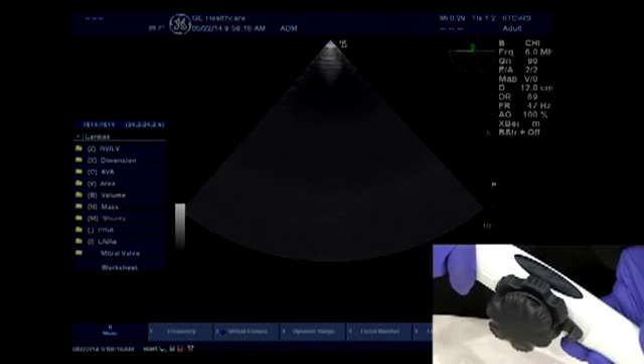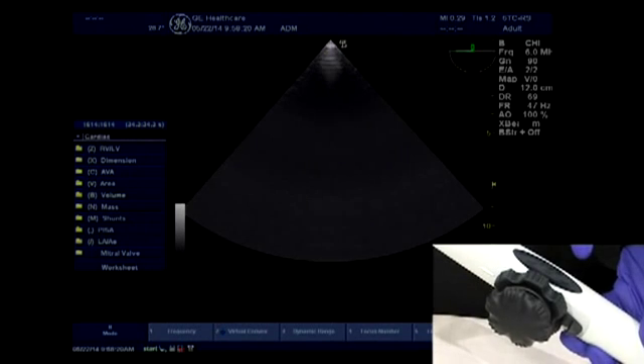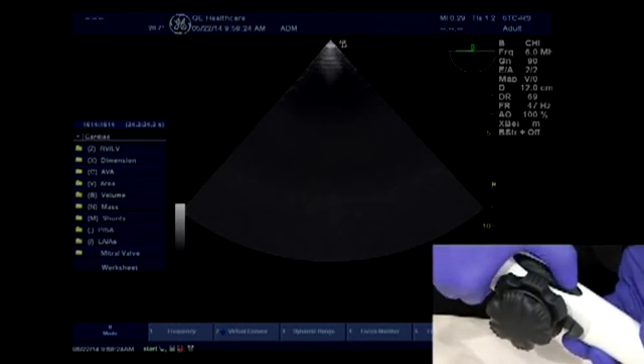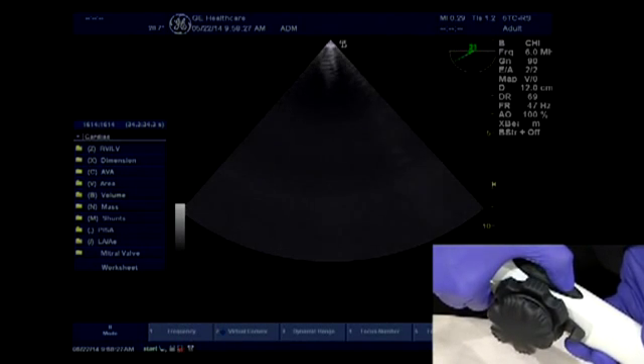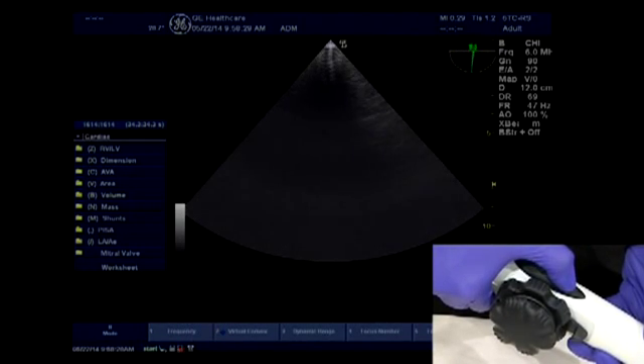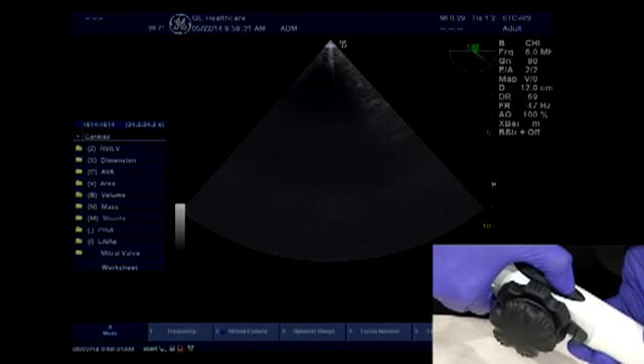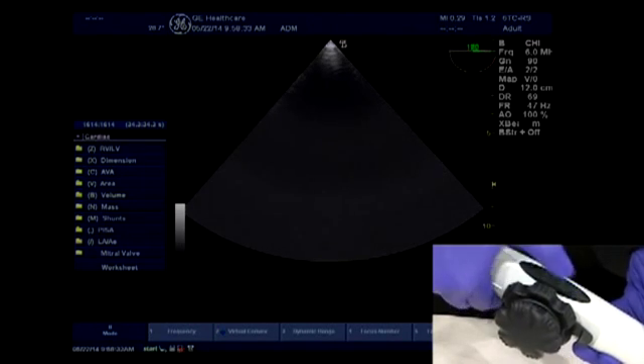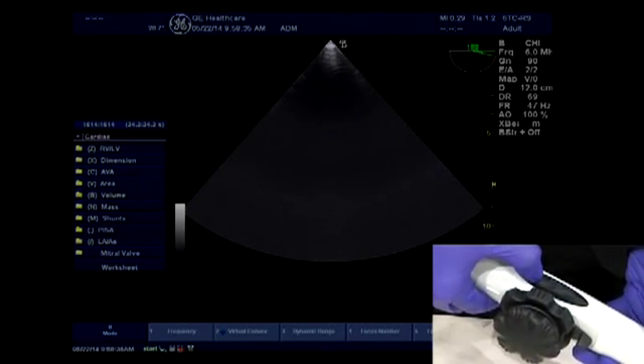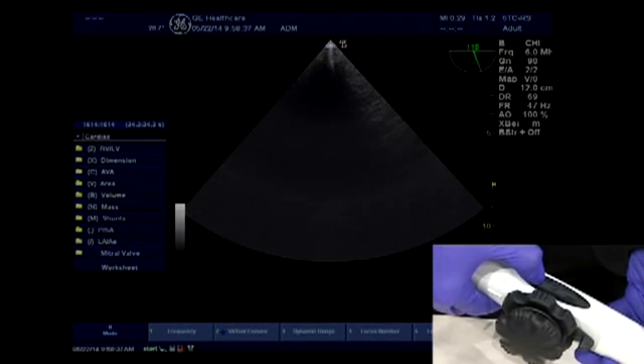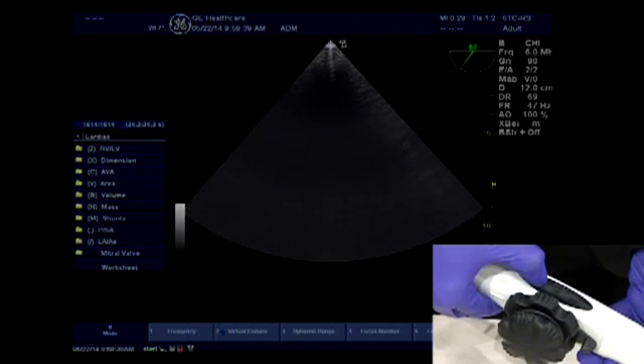Operating the scan plane rotation controls. The scan plane rotation is driven by buttons located on the handle. When pushing the button closest to the probe tip, the scan plane rotates counterclockwise, increasing the angle to a maximum of 180 degrees. When pushing the button furthest from the tip, the scan plane rotates clockwise, decreasing the angle from a maximum of 180 degrees to 0-degree angle.